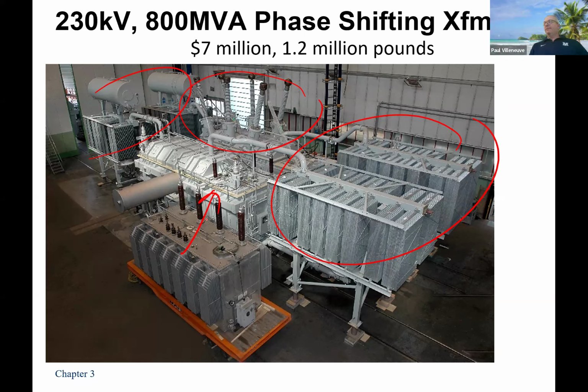For those band things, yeah, these are radiators. It's kind of hard to tell. I don't think there are any fans in here. They just use natural cooling. So you take the oil and you direct it to the outside, and the oil has a bigger surface area, so it has a chance to cool. That's all it is. Not a great design, but the nice thing is this is passive cooling, right? It just relies on the fact that at higher temperatures, the density of the oil is lower. So it floats to the top and the cool stuff goes down. And so that gets directed into the transformer.